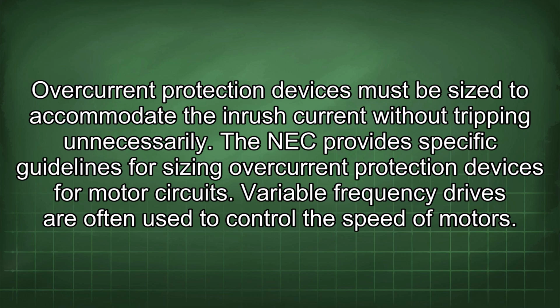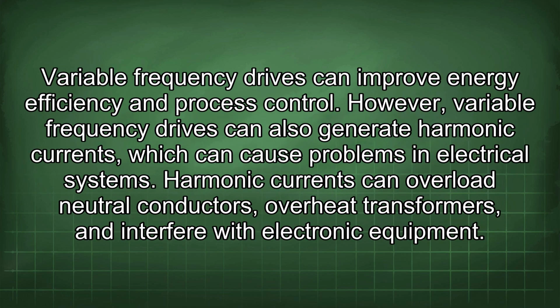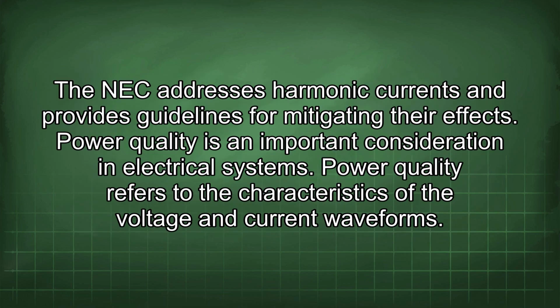Variable frequency drives are often used to control the speed of motors. Variable frequency drives can improve energy efficiency and process control. However, variable frequency drives can also generate harmonic currents, which can cause problems in electrical systems. Harmonic currents can overload neutral conductors, overheat transformers, and interfere with electronic equipment. The NEC addresses harmonic currents and provides guidelines for mitigating their effects.